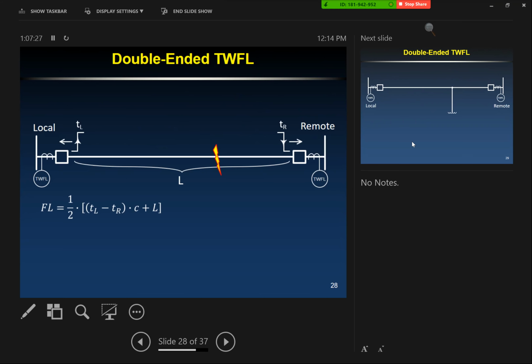You could get a slight difference because we're correcting by that. We're lumping the current transformer secondary lead. Yes. And if one end is real short, one end is real long, that could give you a little difference. But again, that's typically going to be less than 1,000 feet of difference between the two. Right, which is not many microseconds. Yeah, and this formula does not accommodate that CT lead length, but it'll give you close enough in most cases.